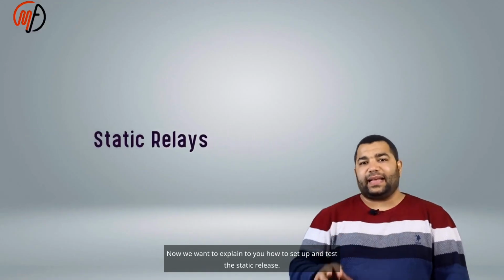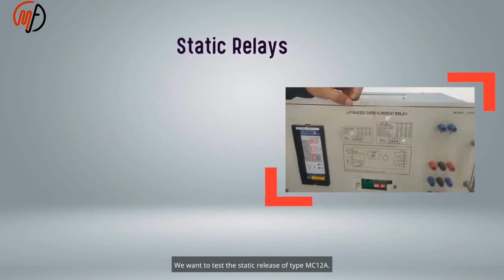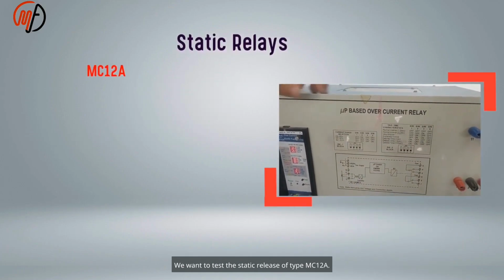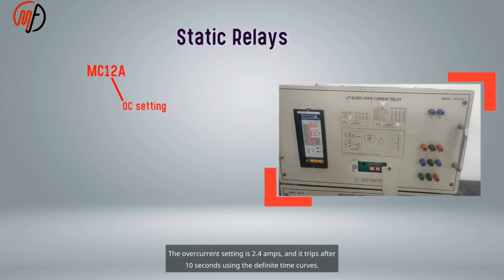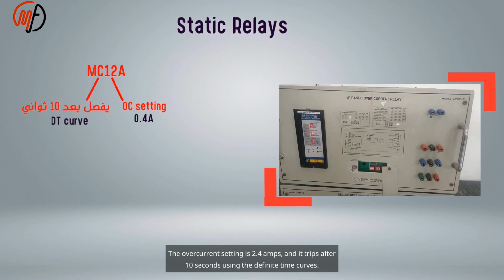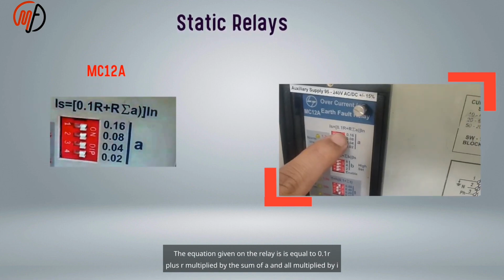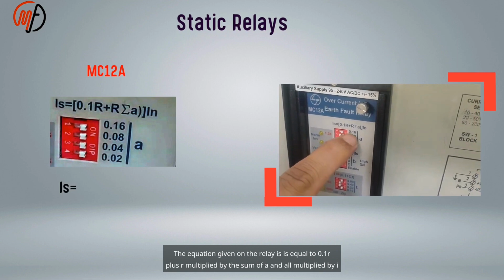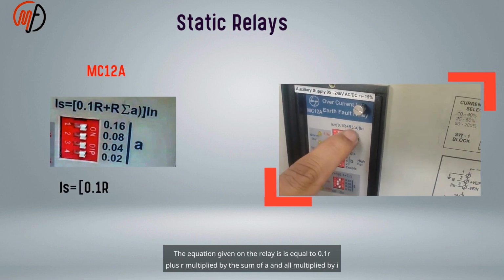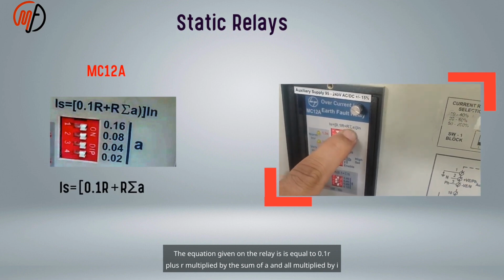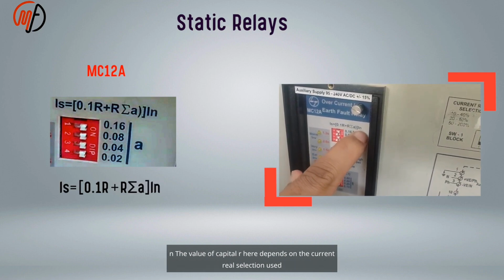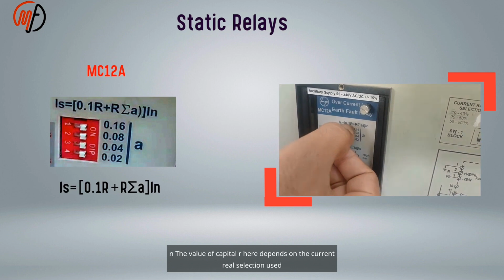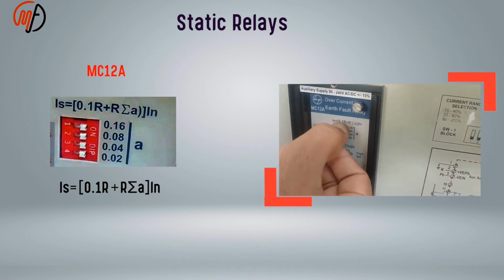Now we want to explain how to set up and test the static relay. We want to test the static relay of type MC12A. The overcurrent setting is 0.4 amps and it trips after 10 seconds using the definite time curves. The equation given on the relay is 0.1 R plus R multiplied by the sum of A, all multiplied by IN. The value of capital R here depends on the current range selection used.